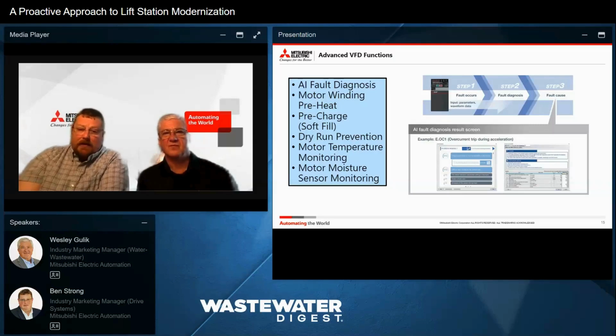Motor temperature monitoring, and we can pull that information into the VFD. We can pump that up directly to the SCADA unit, or we can collect it in a PLC to gather that data and then push it up however we choose to communicate with the overarching control. And that moisture monitor sensor, it's important that we hook that up and then we monitor it, whether that's through the VFD inputs or through a PLC.